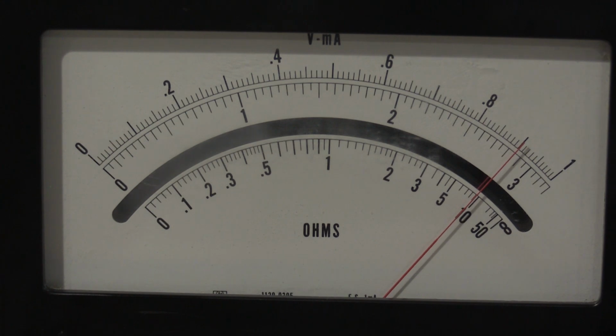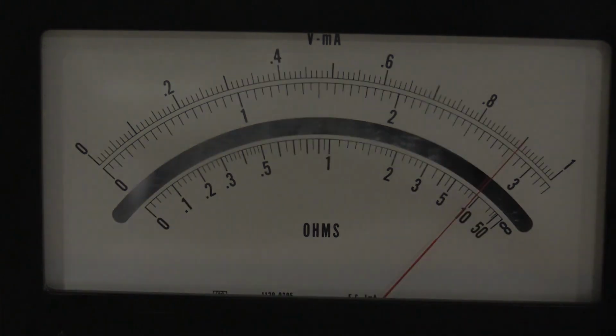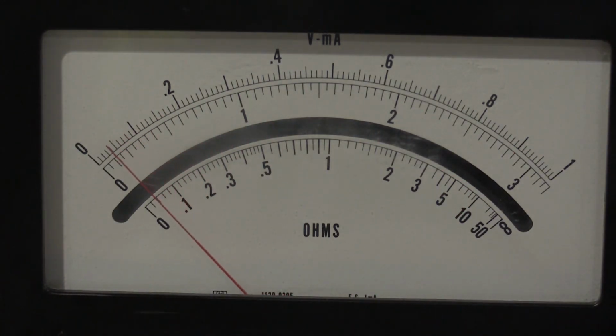And the burden voltages on these are incredibly low. This is 9 milliamps, and the burden voltage on this range is 6.7 millivolts. Where you use a shunt resistor, because this has a high impedance front end, the burden voltage on this meter is much lower than the burden voltage on a handheld DMM. Let's ask for 25 milliamps. That looks good there. My burden voltage on this one is 18 millivolts. So very, very low.